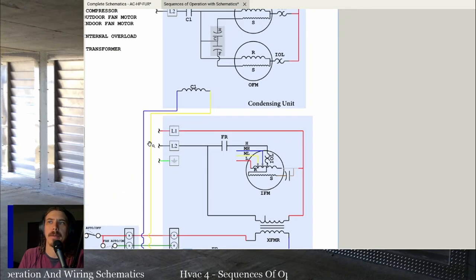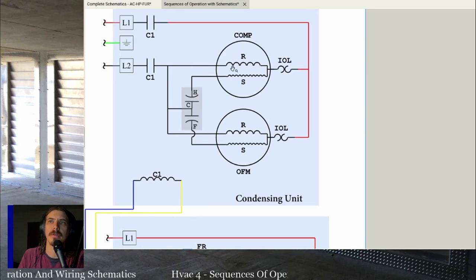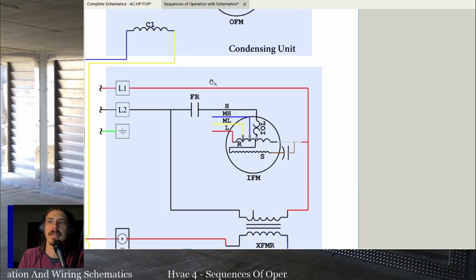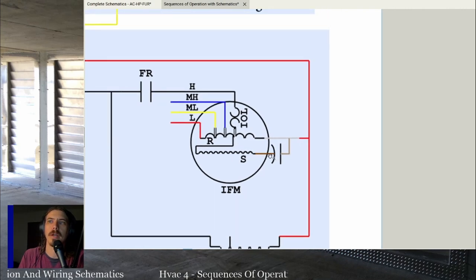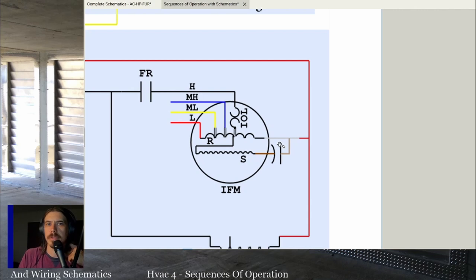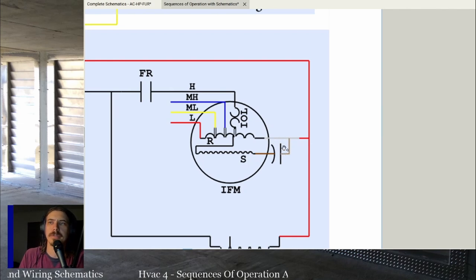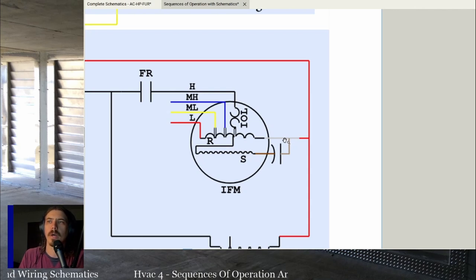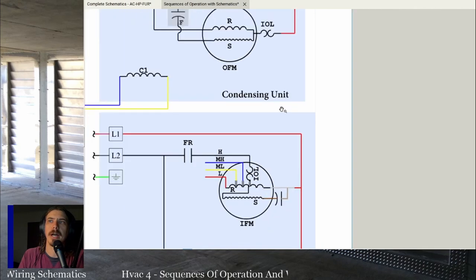Both the outdoor fan motor and compressor are shown in a three-wire configuration to the capacitor. The indoor fan motor is shown in a four-wire configuration — the brown wire goes to one side of the capacitor and the brown-and-white wire goes to the other side, which is just tied on to the common wire. You could just wire this in three-wire; you've probably seen condenser fan motors wired three-wire or four-wire. Either way, any motor can be wired three-wire or four-wire — the brown-and-white is simply jumpered to the common wire.